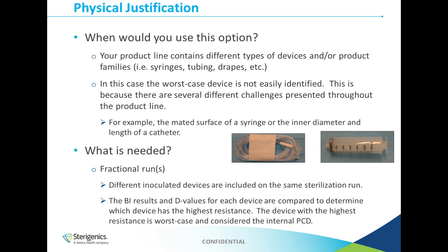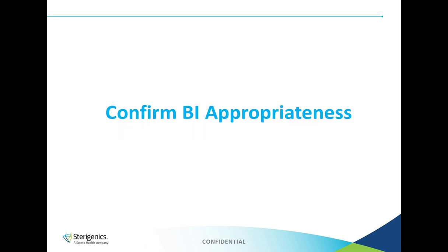Now, off of this fractional run, you're going to look at the BI results and you're going to calculate the D values for each device and compare them to determine which one has the highest resistance. And this device that has the highest resistance is going to be your worst case and it's going to be considered your internal PCD.